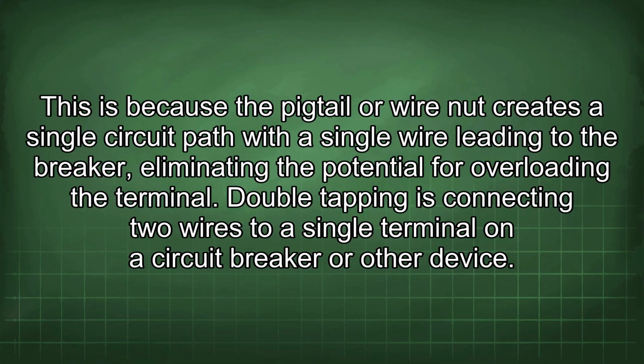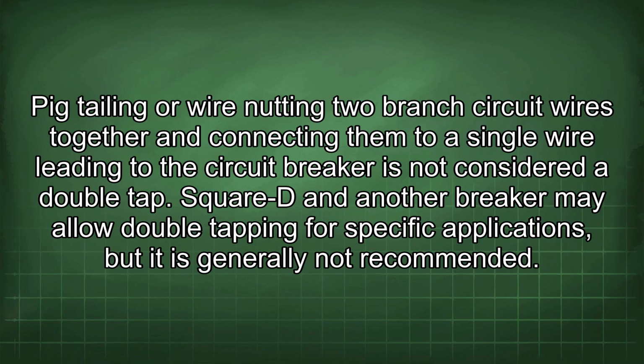Double tapping is connecting two wires to a single terminal on a circuit breaker or other device. Pigtailing or wire nutting two branch circuit wires together and connecting them to a single wire leading to the circuit breaker is not considered a double tap. Square D and another breaker may allow double tapping for specific applications, but it is generally not recommended.